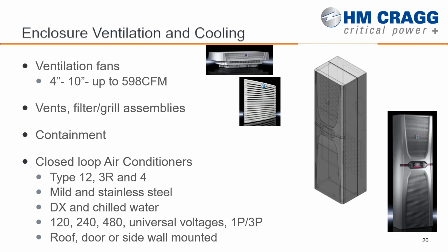Cody's done some design work. Everybody on the phone, I'm assuming, knows hot aisle, cold aisle, where you add containment on a row of racks. Well, we've taken that same concept and integrated it inside of some of the larger UPS assemblies so that we can create kind of a dead space, and we don't get hot air and cold air mixing through the enclosure, which makes the air conditioner much more efficient as it's trying to take care of all the heat coming off the UPS. So we actually add this plenum in order to eliminate that mixing.